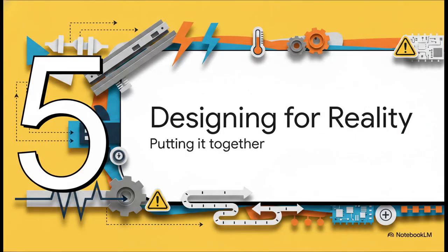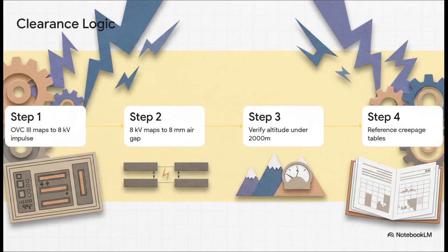All right, we've reached the final phase, Section 5, Designing for Reality. Okay, let's put it all together. We're going to combine all these standards, voltages, and real-world variables into a practical logic chain for a standard 1,000-volt distribution panel. Step 1. Fixed distribution equipment like switchboards fall under overvoltage category 3, which maps out to an 8 kilovolt impulse duty. Step 2. That 8 kilovolt impulse directly translates to an 8 millimeter minimum air clearance gap.